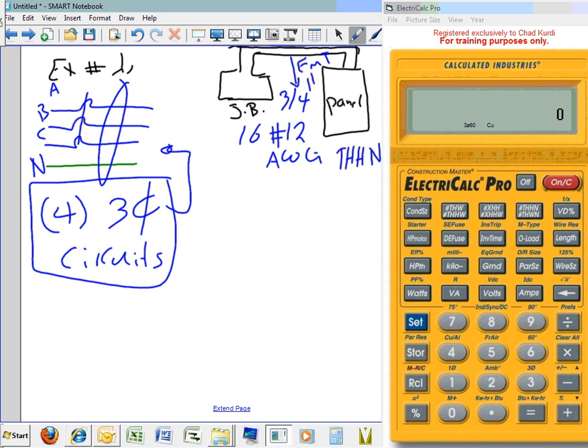So what am I going to do with these 16 conductors? I don't pull conductors for the sake of pulling conductors. I am taking 3-phase and neutral to feed receptacles and or lights, depending on the voltage. If the voltage is 120, it could be receptacles and or lights. If the voltage is 277, 99% of the time you're feeding lights. So the voltage is irrelevant. Okay, everybody see what we're doing?